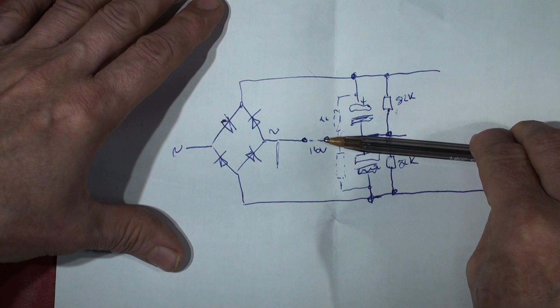Now I've just turned the unit on and found these voltages. I always check this voltage whenever I turn something on. I'll put it on the lower voltage on the variac via the isolation transformer, and then we check the voltage to make sure they're more or less the same. They should be within 4 or 5 volts, or even a couple of volts, of each other on a good circuit.